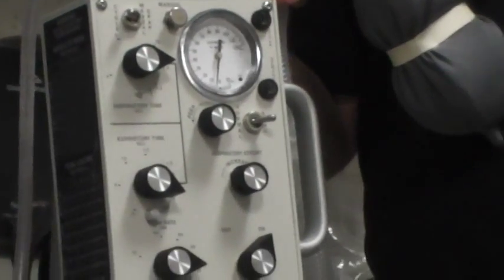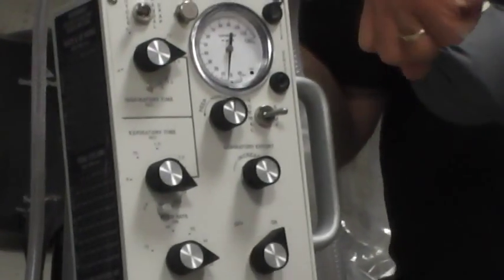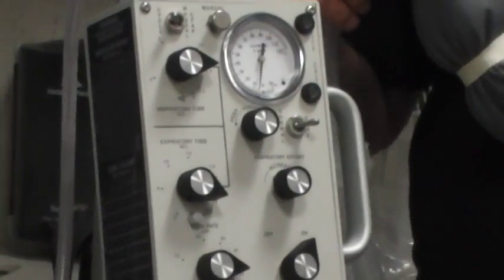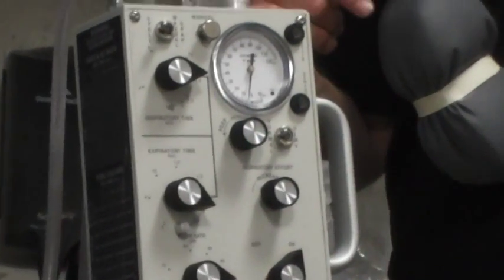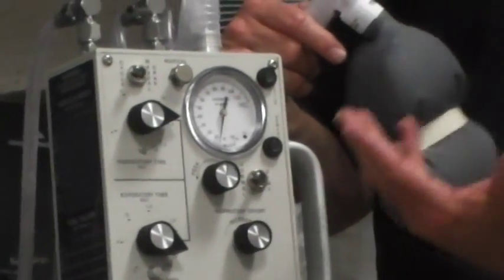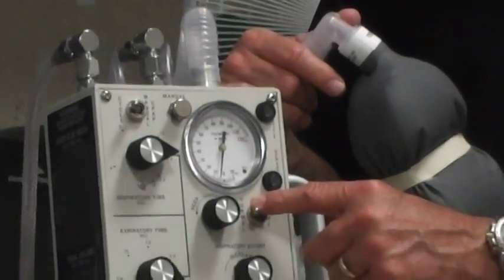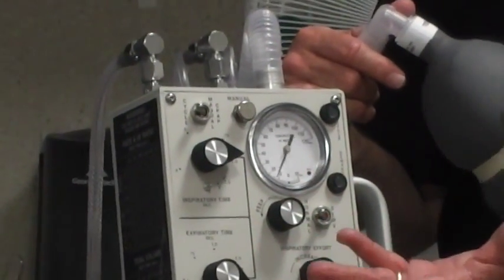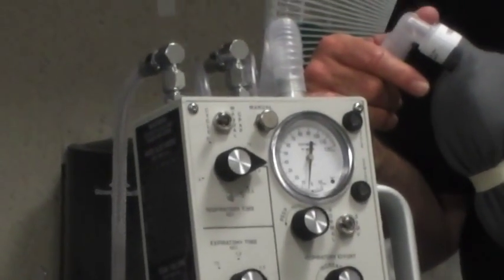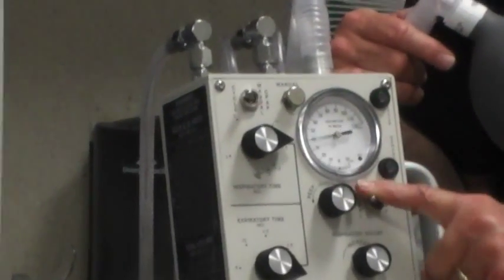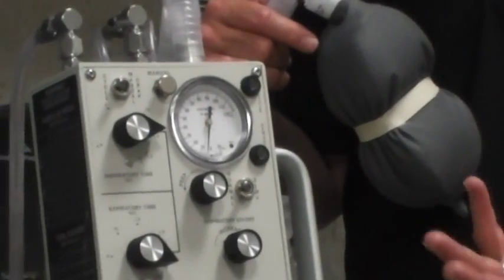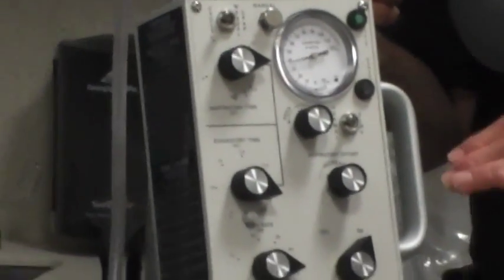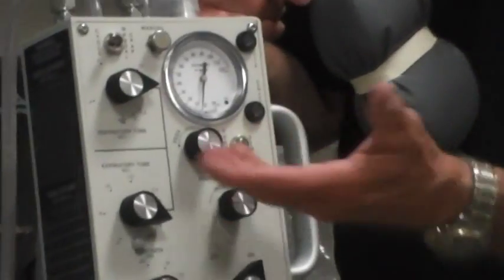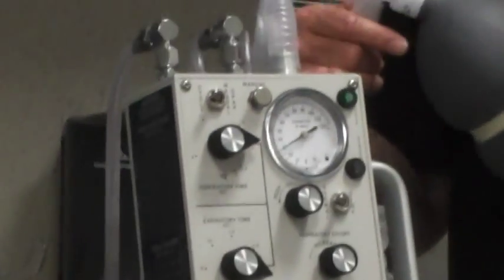So there's a couple ways you can handle that. You can stop the MRI, get the patient out of there, get an AMBU bag, and save them. Or all you need to do is flip the switch, because if they stop breathing, they're going to get a rate of 12. Now I keep the test going. So that's really all you have to do. I think what most people decide is, you know what, we don't want to mess with it. Let's leave them on normal or assist control. And maybe that'll be the safest thing to do.